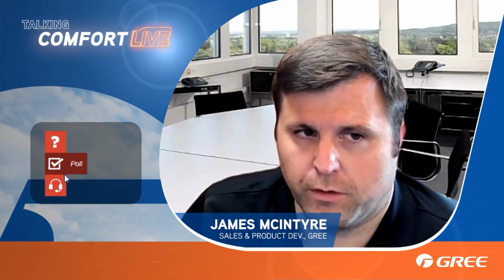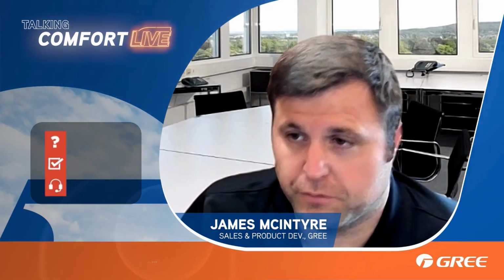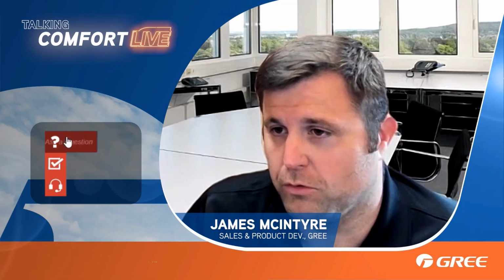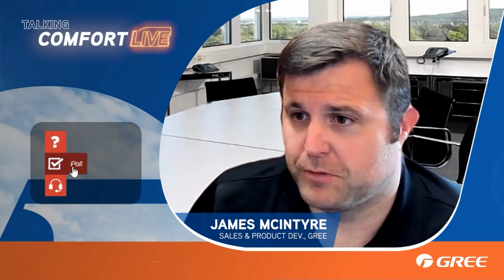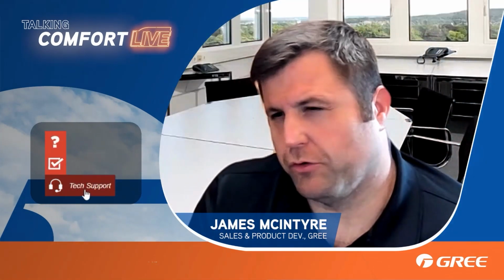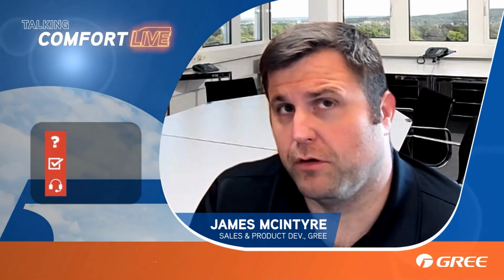Right. And I know we're talking about 15 years ago, 20 years ago on heat pumps, but I think one thing we should keep in mind is that many of the heat pumps still on the market right now are based on those designs, and they still do lose efficiency starting at 47. You're absolutely correct. Unfortunately, I overlooked that when I made my statement. Many of them still today are on that same design platform, and they aren't really producing any better heat than they used to 15, 20 years ago when you get below 32 degrees. Right. On a 4-ton regular traditional style heat pump, you can lose 1 ton of heat from 47 to 36, depending on the manufacturer design and all that kind of stuff.